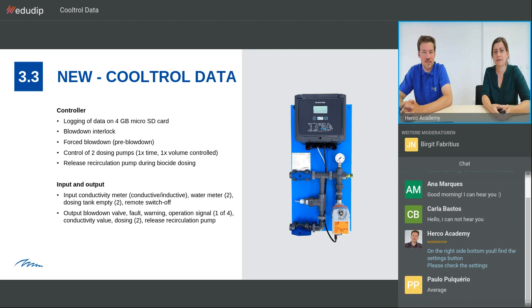This is because requirements in Germany, and most probably other countries too, require the operators in most cases to log the data from the cooling tower system. This is, for example, also because in some cases there have been Legionella outbreaks because of cooling towers that had been badly maintained. So this should be avoided in future, and that's why people have to log their data as well. Apart from the data logging, we have the functions that you will know from the Cooltrol controller already.